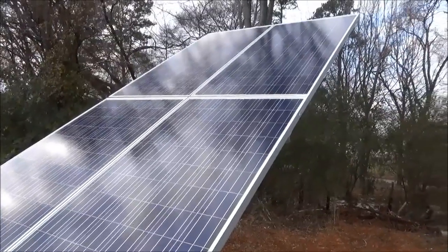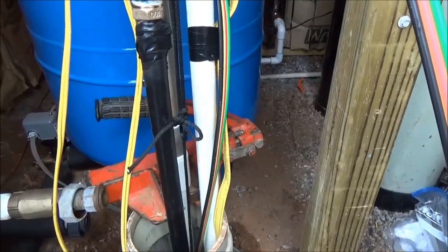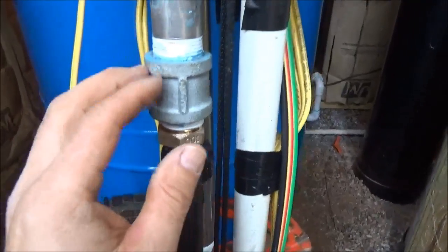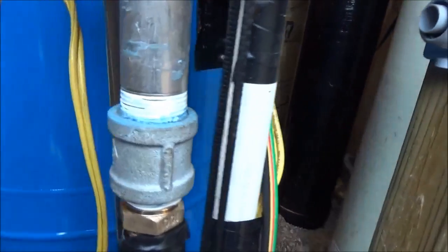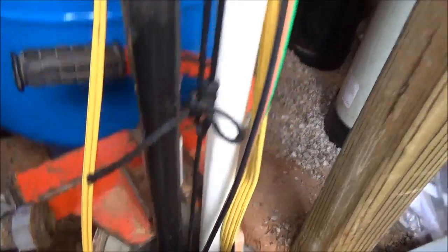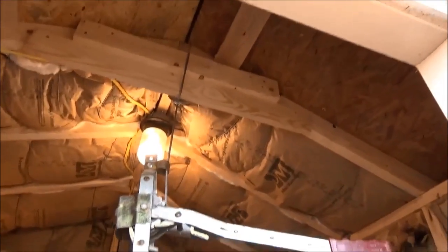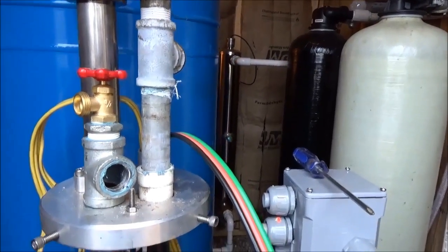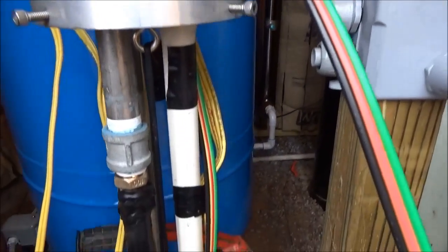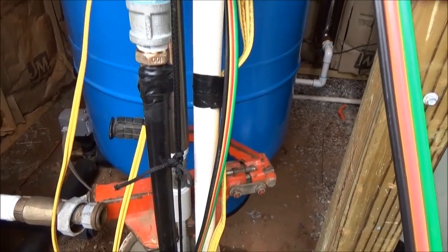Just showing you a little bit of what goes below the well seal. We've got the solar pump, the standard one-horsepower grid pump, and the Simple Pump — which I'm clamped off to with our well safety clamp. We made a little rig with our come-along to hold the well pump up while we set everything back down. There are three drop pipes, two sets of wires, safety ropes, and a lot to consider.